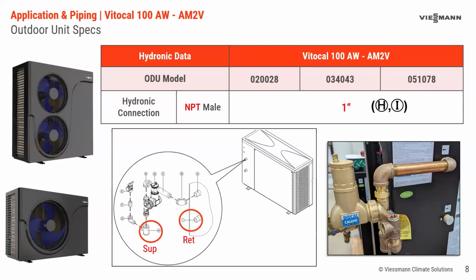So the first thing we're going to look at is the outdoor unit and the connections. All the connections in the outdoor unit are all 1 inch, and you can see the H and the I referring to the drawing here. The native connections on the unit are 1 inch, but so is the air scoop and the pressure relief valve. That whole area ends up with a 1 inch termination. Now, that's not to say you're going to use 1 inch pipe for every application. This is just an indication of where we're starting with. And again, they'll go through the details of pipe sizing in a future webinar so that you can get pressure drop and friction loss and those kind of things.